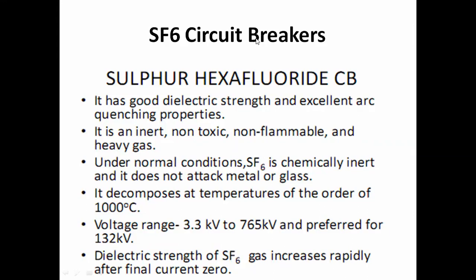But why can we use this sulfur hexafluoride gas? Because this gas has certain advantages, due to which it can be used as an arc quenching media to quench the arc between the moving contact and the fixed contact when the circuit breaker is operated. There are a few properties of sulfur hexafluoride gas due to which we can use it in a circuit breaker. It has good dielectric strength and excellent arc quenching property. So due to good dielectric strength as well as high arc quenching property, this type of gas is used for arc quenching in circuit breakers.